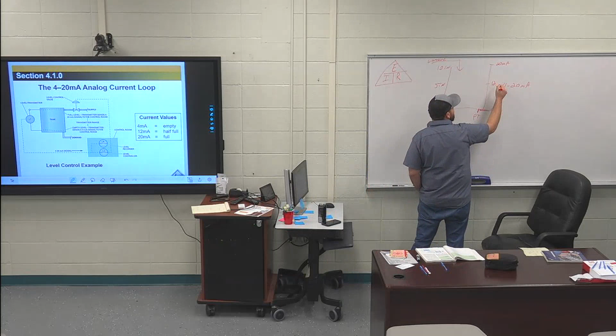A lot of people think 20 minus 4, 16 divided by 2 is 8, but you have to re-add your 0, so 8 plus 4 is 12. So if I'm at 0 inches, it's going to show 4, 5 inches, 12, 10 inches, 20, and then everything in between. So all that's saying is that your analog signal is going to vary proportionally with whatever the process liquid is that's in this. So it'll go up and down. It should go up and down the same proportionally.